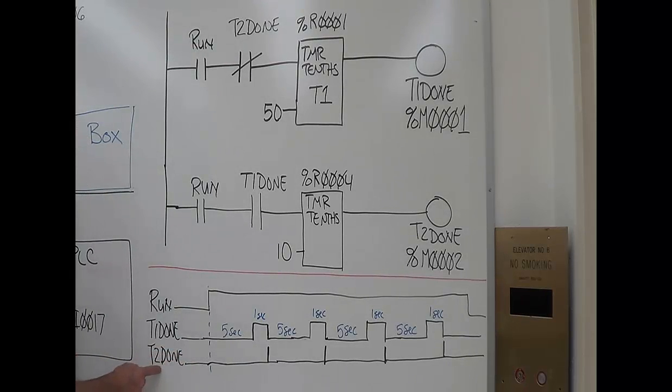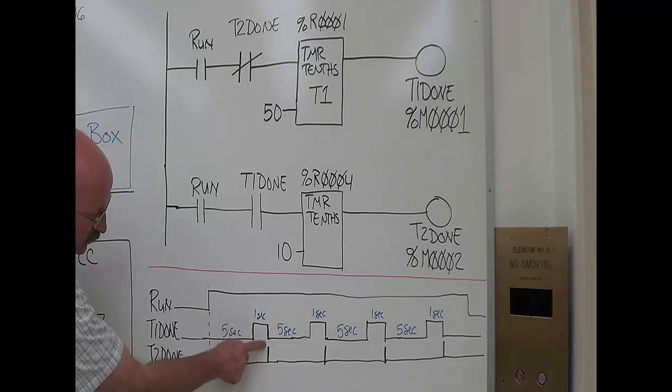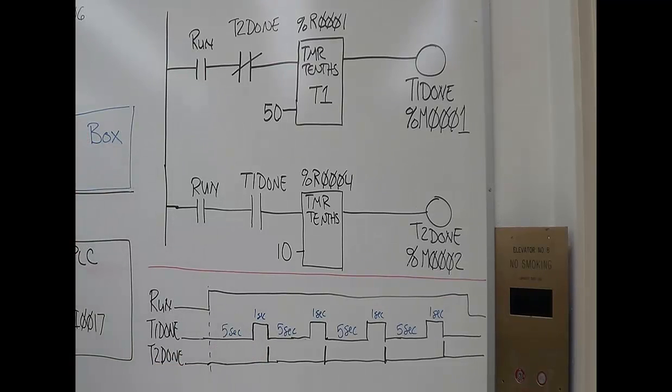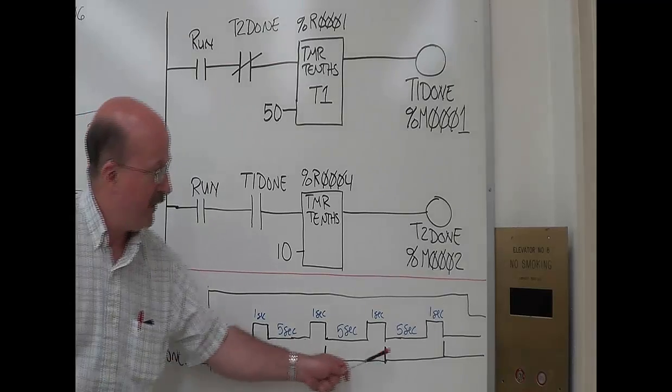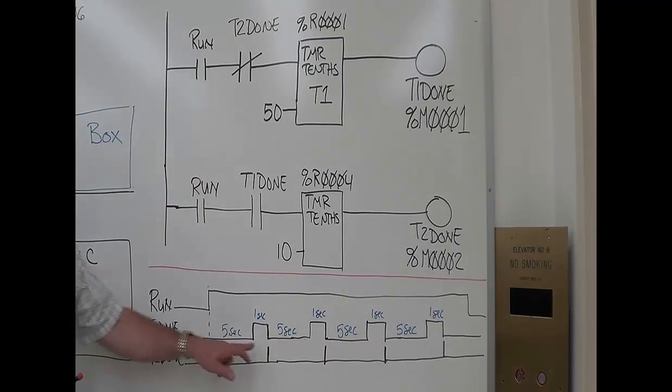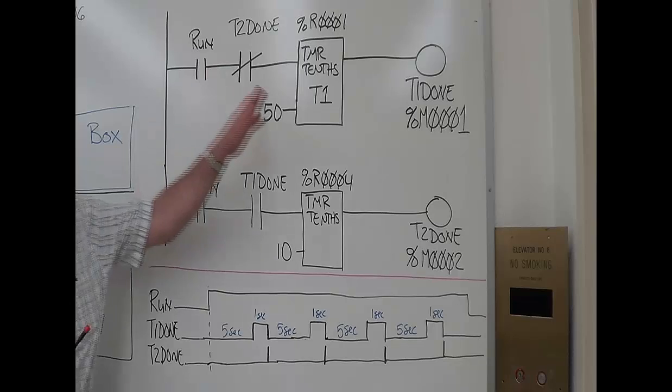What happens if you look at timer 2 done, I show its output going true as just a line. One single line right there, here, here, and here. That's indicative of the output just going true for one scan.